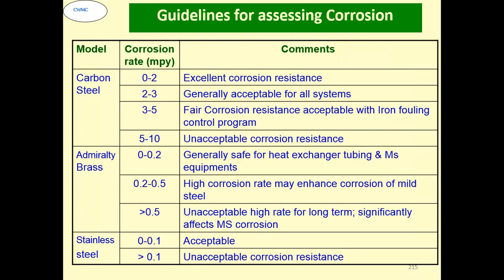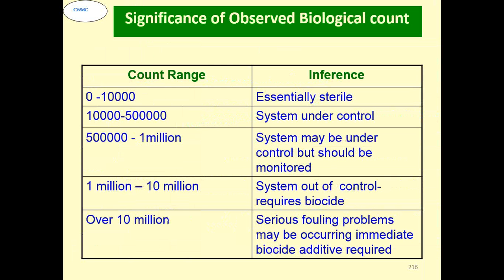Assessing corrosion: for carbon steel, less than 2 is excellent, 2 to 3 is acceptable, 3 to 5 is fair corrosion, 5 to 10 is unacceptable. For admiralty brass similarly 0.2, actually it should be 0.1, now it has been modified to 0.1, and for stainless steel again 0.1. Bacterial biological count: 0 to 10,000, essentially a sterile system. 10,000 to 5 lakh, system under control. 5 lakh to 1 million, system may be under control but should be monitored. 1 million to 10 million, system out of control, requires biocide. Over 10 million, a serious fouling problem may be occurring, immediate biocide addition required.